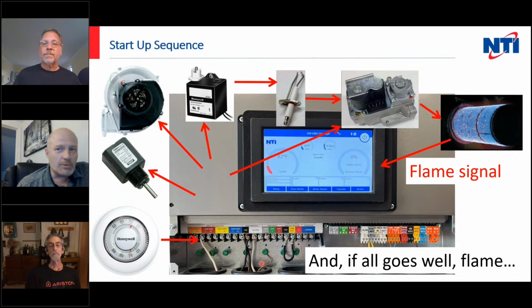One thing that sometimes throws people off is they'll look and see a flame, but they forget that the boiler needs to see that flame as well. You've got to remember that the flame rod is the boiler's eyes. It's not as bright as you are, so it can't see the flame except through the flame rod.